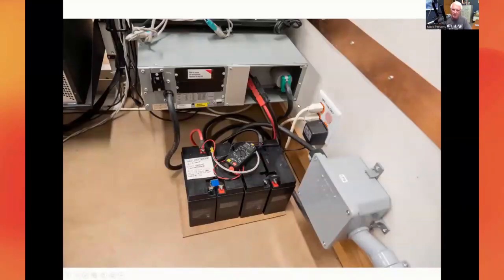Let me show you the batteries for the UPS. Instead of leaving the batteries in the UPS, I set them out in the back because I found that batteries run warm in cabinets like a UPS, and their life is reduced. So in this case, I have them out so they stay nice and cool. I put a voltmeter on them so I can watch them. When I do a test, I can watch the voltage drop, and if it drops more than I think it should, then the batteries get replaced. That voltmeter had to be powered by a wall wart transformer. No big deal, but that's just the way it is.